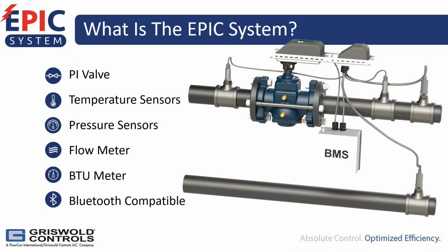So what is the EPIC system? The heart of the EPIC system is the Griswold Controls pressure-independent valve, and a pressure-independent valve is an actuated valve that modulates to some reduced load position, and then once the valve is done modulating and the load is satisfied, any change in system pressure does not impact that flow. And so a pressure-independent valve is important because it saves from constantly having to reposition and remodulate to a different position because there's been a pressure change in the system.